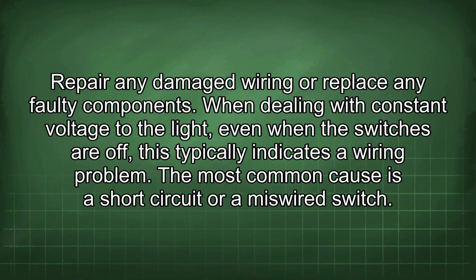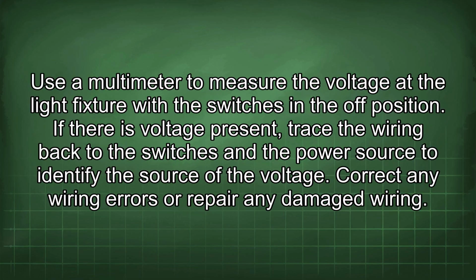When dealing with constant voltage to the light, even when the switches are off, this typically indicates a wiring problem. The most common cause is a short circuit or a miswired switch. Use a multimeter to measure the voltage at the light fixture with the switches in the off position. If there is voltage present, trace the wiring back to the switches and the power source to identify the source of the voltage. Correct any wiring errors or repair any damaged wiring.